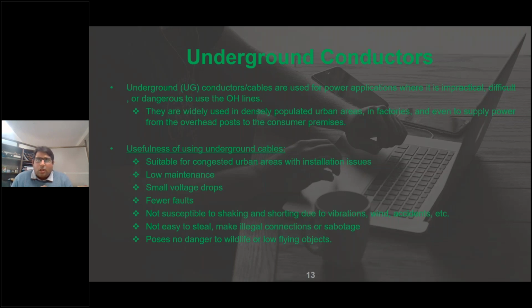They are low maintenance, and the losses or trippings are very low compared to their overhead counterparts. They have a small voltage drop. Usually the overhead conductors we have in use may have a voltage drop of up to 3% depending on the length of the line. However, for underground cable the voltage drop is comparatively less; we checked, and it was less than 1% for 1.5 to 2 kilometers. There are fewer faults, and they are not susceptible to shaking and shorting due to vibrations, wind, or accidents, to which the overhead counterpart may be susceptible. They are not easy to steal from or to make illegal connections on, like pilferage or direct kunda connections. They cause no danger to wildlife or to low flying objects like helicopters or drones.